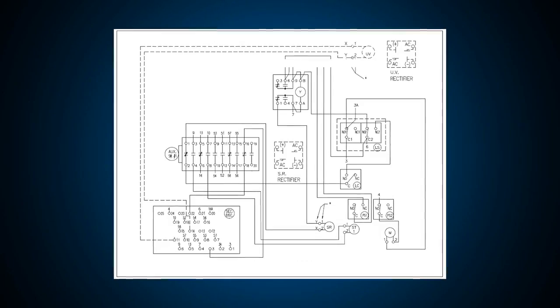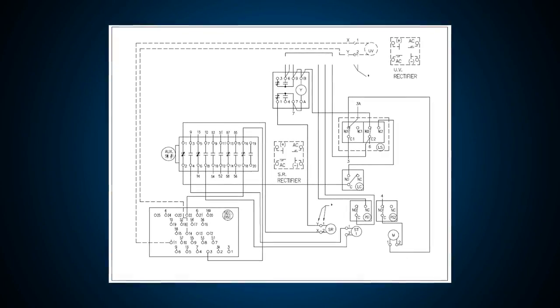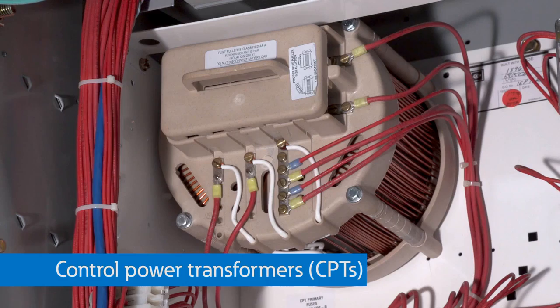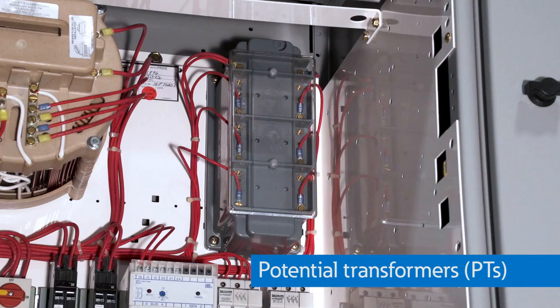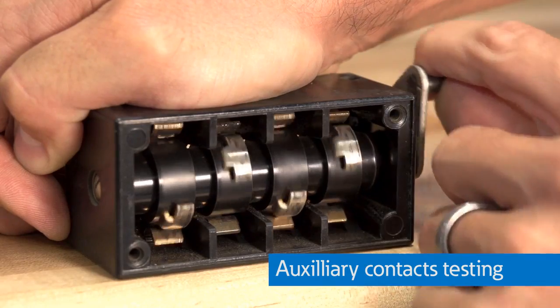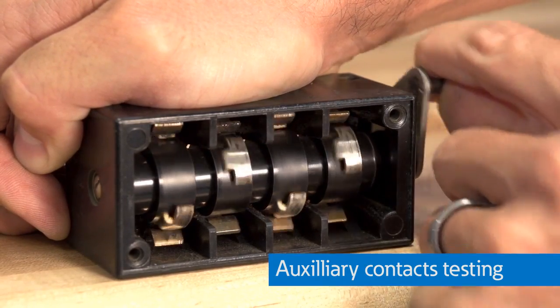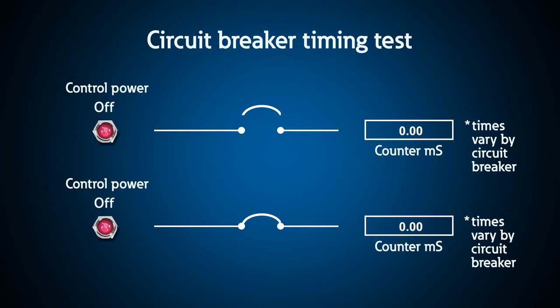For this test, you verify that all wire connection points are landed in the appropriate locations when comparing them to schematics. Control power transformers, or CPTs, used for supplying power to control equipment, and potential transformers, or PTs, used to monitor voltage, must be checked to verify expected voltage levels and functionality. Auxiliary contacts must be tested to verify that all contacts make and break at the correct time. Also, contact resistance should be verified to ensure you have a good low resistance for each contact. Finally, timing testing will help you verify that contacts open and close in the proper amount of time and in sequence after receiving a control signal.